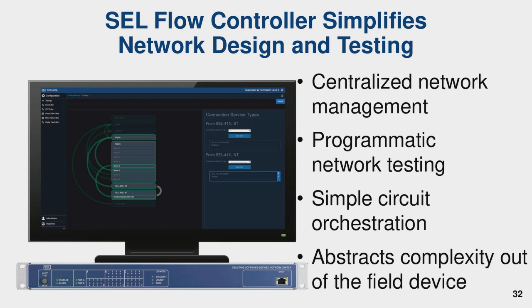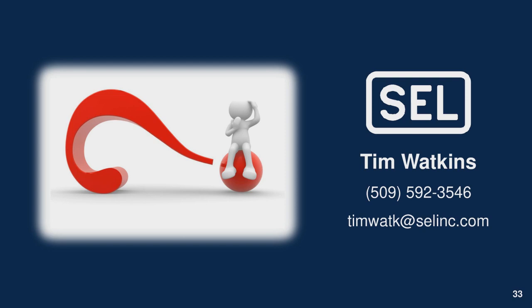To summarize, the SDN flow controller provides centralized network management, programmatic network testing, and when a link fails, we know the secondary path length, which we can deterministically provide to protection engineers so they can account for the timing difference between primary and secondary paths. It gives you simple circuit orchestration — visibility of packets, how circuits are being used — and extracts complexity out of field devices to make the system more usable as well as more secure. That concludes my slides. I'm ready for questions.